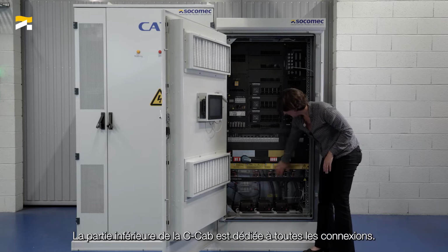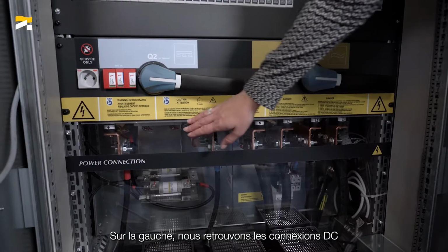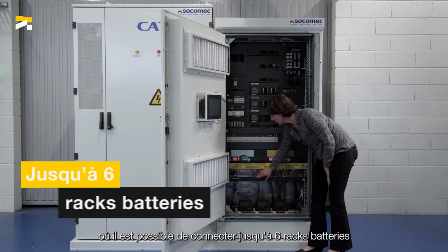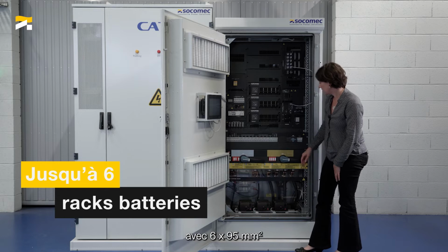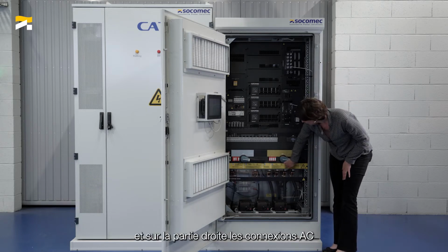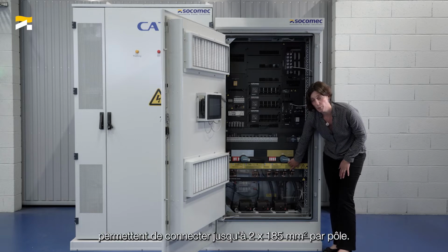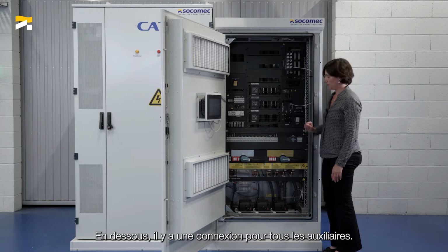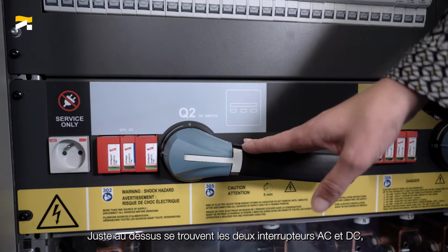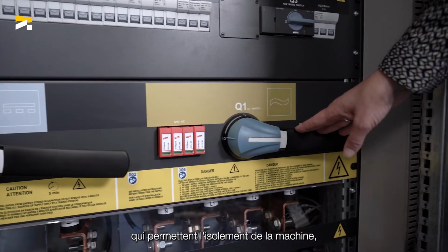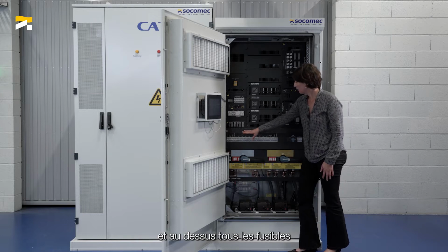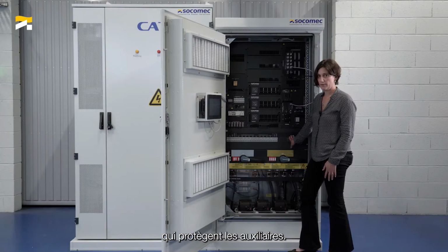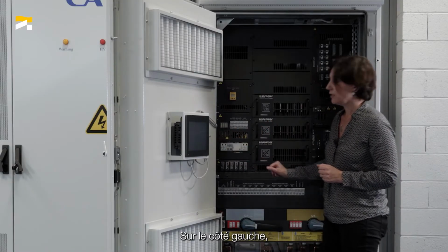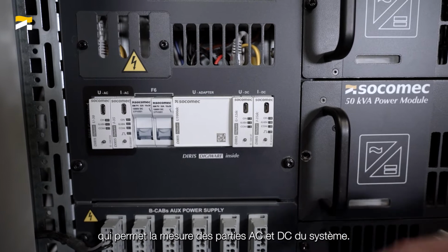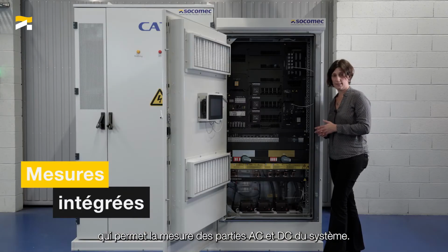So, the bottom part of the C-cab is dedicated to all the connections. On the left side is the DC connection, so we can connect up to 6 battery racks with 6 × 95 square millimeters. And on the right side, we have the AC connections with up to 2 × 185 square millimeters per pole. Below this, we have the auxiliary connections. Just on top of it, there are 2 switches, AC and DC, that enable the machine isolation, and on top of it, all the fuses to protect the auxiliaries. On this left side here, we have a DIRIS Digiware integrated that will enable the measurement of all AC and DC parts of the system.